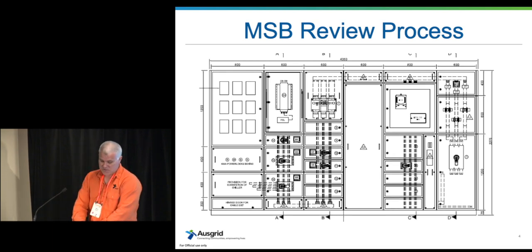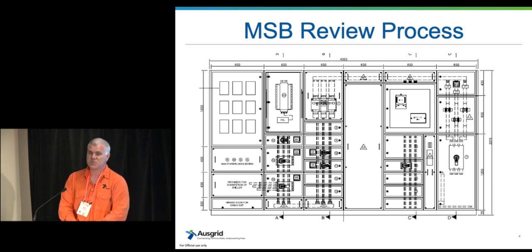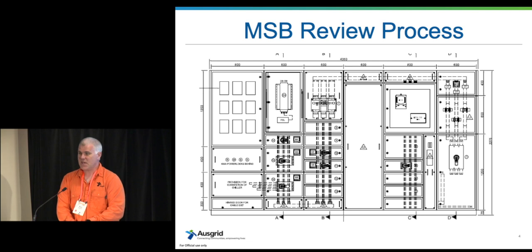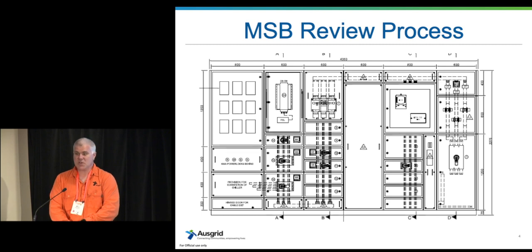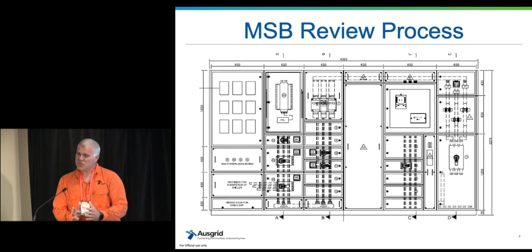So as you could appreciate, generally our senior inspectors will review one of these drawings on a screen, and we're supposed to get a rough idea of what this switchboard is going to look like. As you can imagine, we're looking at a 2D object there, let alone on the day when we're turning up, looking at a switchboard that's actually constructed that we can touch and play with. So often my IIs will get a bit of hesitation when they identify that there is an issue with the switchboard, and they'll go, but this has been approved already. Later on, you'll see there are no approvals that we get by looking on a computer screen. It does not tell us what you're actually going to deliver. That there is going to be revision A, and it's probably revision G by the time it's actually on site.